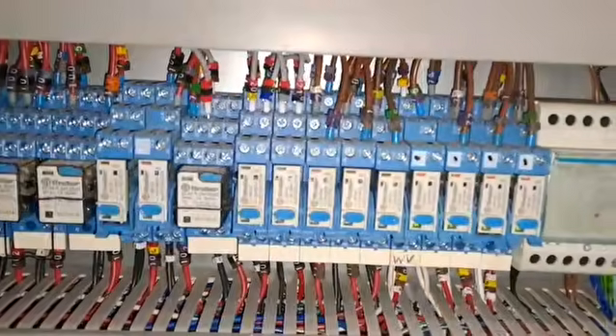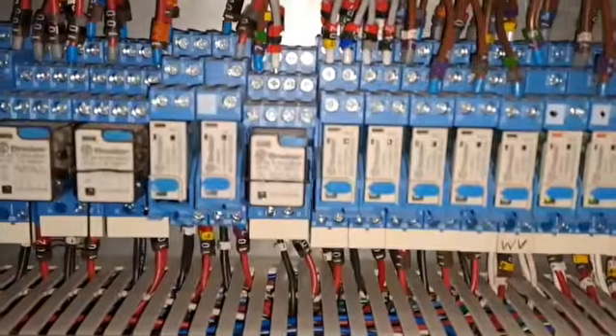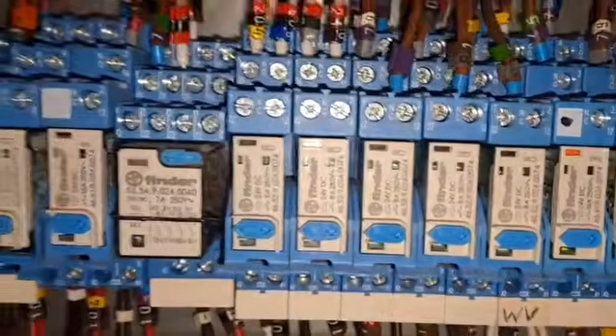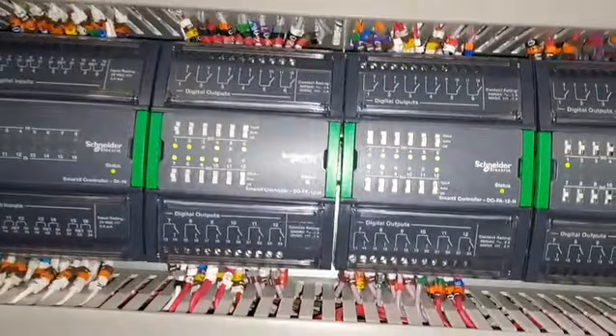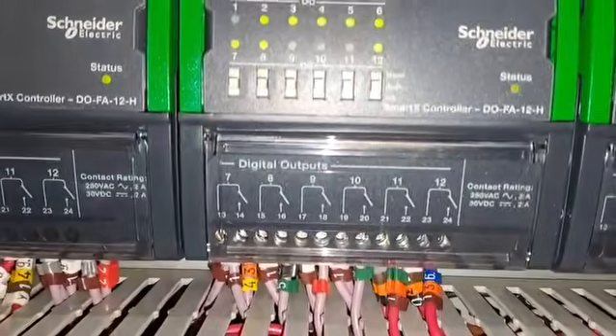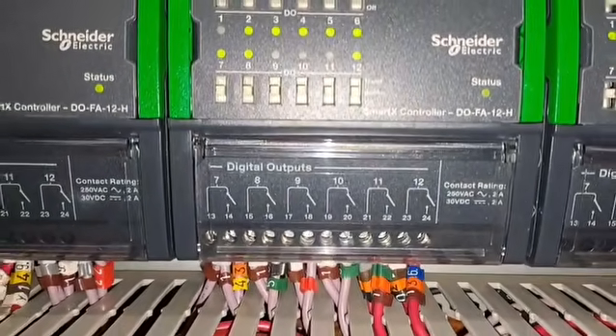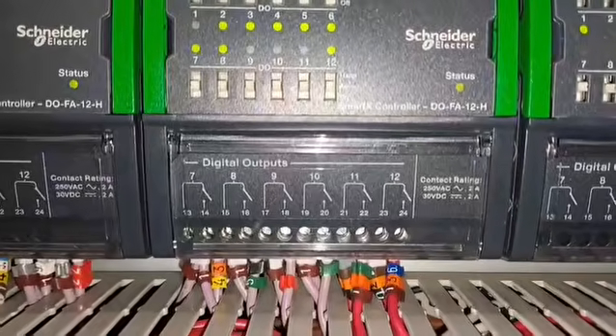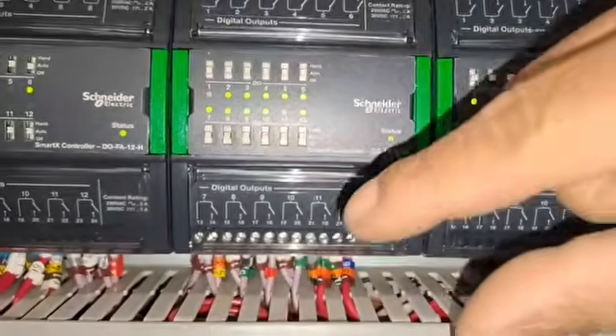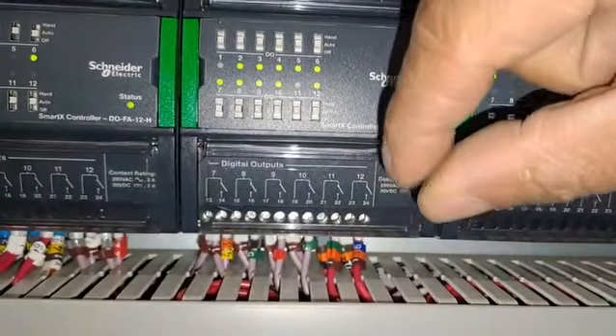We've got a lot of relays here. There's a lot of relays with their little bypasses on them. Don't flick these unless you're sure what you're doing. Relays everywhere. I don't see many contactors. And then this is the Schneider DDC controller, and you've got the digital outputs there in a normally open position, so when there's power to them they will close. So they're open, and then when power gets to them they close.